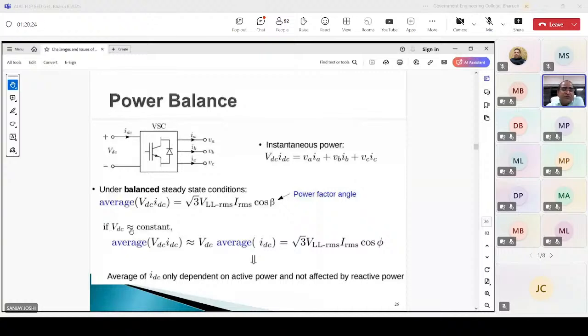Now, if VDC is almost constant, the variation is not really very high. It may have some harmonic, but the magnitude of harmonics in the voltage is very low, so you can consider VDC as constant. So the product of VDC and average IDC is root 3 VLL RMS, IRMS, cos phi. So average of IDC is only dependent on active power and not affected by reactive power. From this equation we can conclude this: the current drawn by VSC, which is IDC - the average of this IDC depends only on the active power.